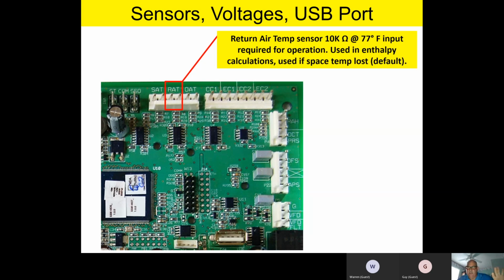Now, this is presuming you're not on a conventional thermostat. You're like on a building management system, or you're driving the unit by the user display, not a thermostat. What will happen, it'll look at return air temperature, and you can actually operate the equipment on return air temperature if you don't have a space temperature sensor or the thermostat fails. And so this is required for operation. So make sure that, again, that sensor is viable when you're doing your troubleshooting.